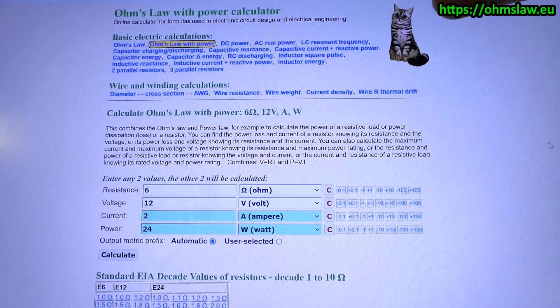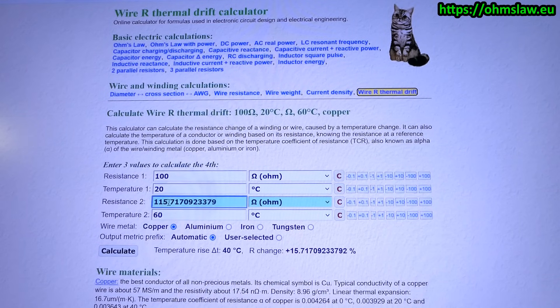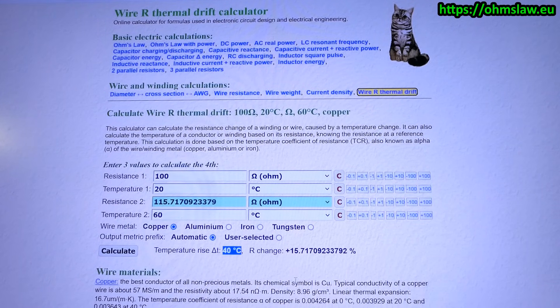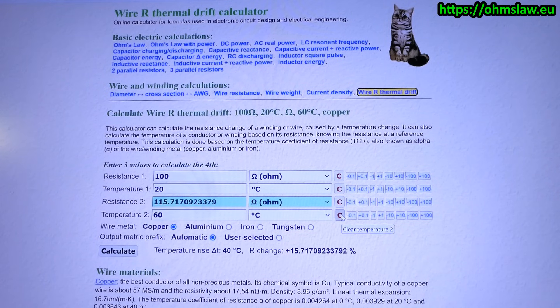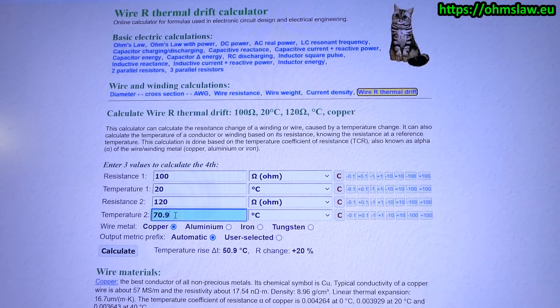Let's take a look at the calculator. For example, a wire or winding with a 100 ohm resistance at 20 degrees Celsius will have about 115 ohms at 60 degrees Celsius — basically a 40 degree temperature rise — and the resistance increased by 15 percent. You can also go the other way: if you measure that the resistance increased to 120 ohms, you can calculate the second temperature, which comes out as 70.9 degrees Celsius.